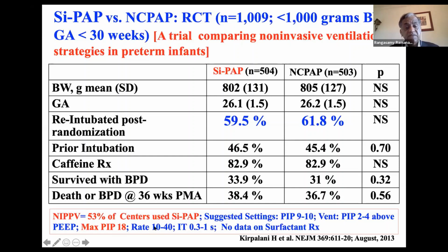And rate 10 to 40. You cannot use a rate of 10 and be successful. You have to start with a high rate whenever you are doing non-invasive ventilation, and then wean the baby to lower rates. Inspiratory time, 0.3. That's not going to work. You need at least 0.5 seconds if you're using non-invasive ventilation, either NIPPV or BiPAP. And no data was given on surfactant treatment.